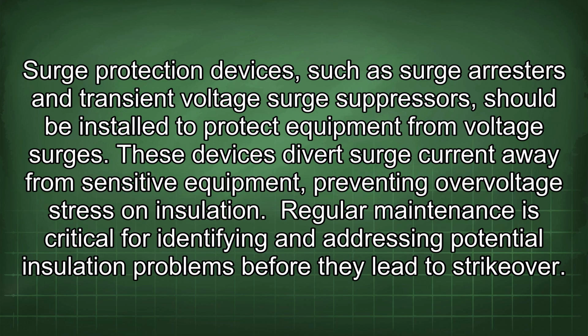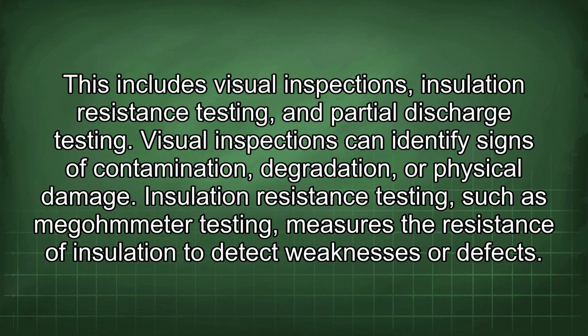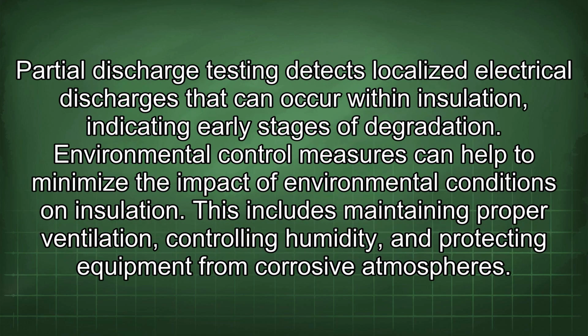Regular maintenance is critical for identifying and addressing potential insulation problems before they lead to strikeover. This includes visual inspections, insulation resistance testing, and partial discharge testing. Visual inspections can identify signs of contamination, degradation, or physical damage. Insulation resistance testing, such as megohmmeter testing, measures the resistance of insulation to detect weaknesses or defects. Partial discharge testing detects localized electrical discharges that can occur within insulation, indicating early stages of degradation.